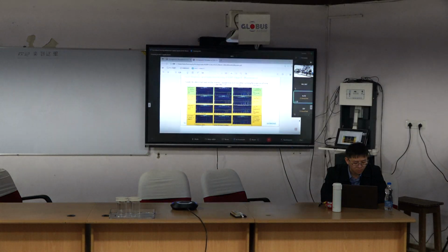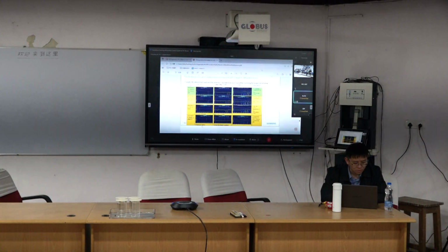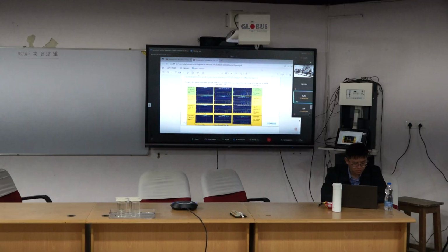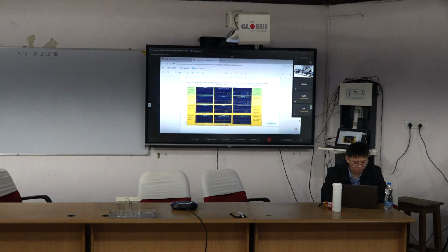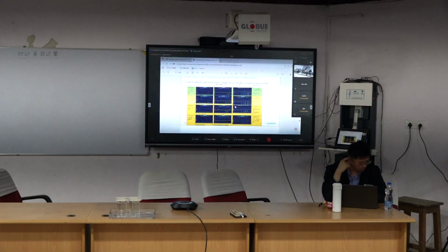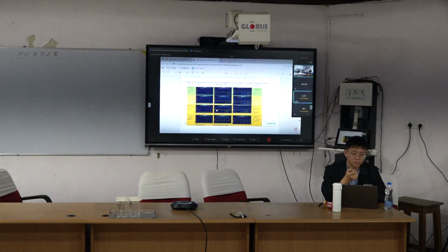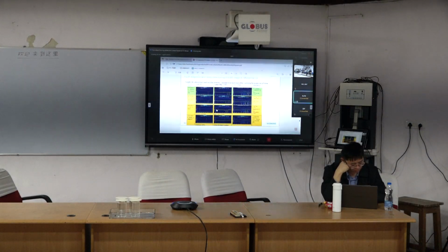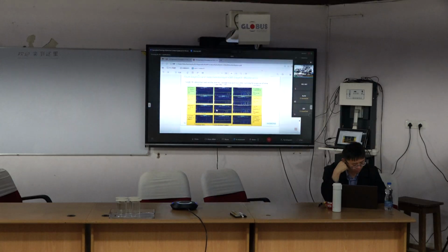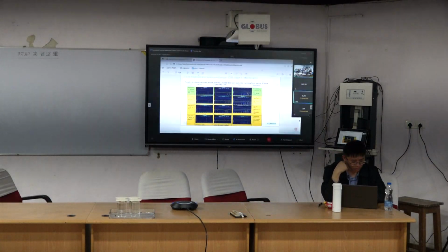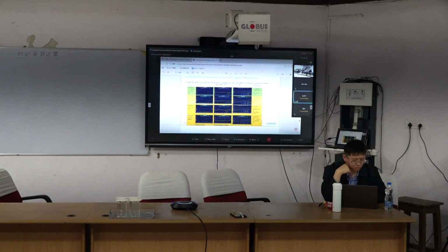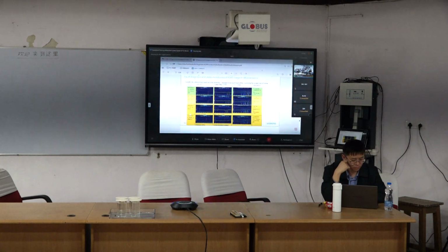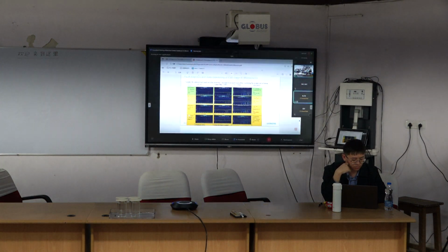This is an overload of almost two times, and the temperature alarm threshold is reached. During operation, everything is okay, no fault happens, no stop, but after running for a period of time, this module will be broken. Actually, in the field, this module failed.